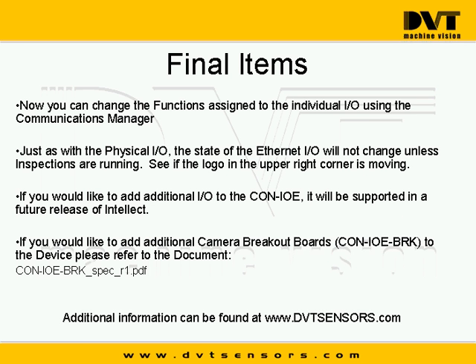Can you say that again about the Modbus? How that's going to communicate? It's going to actually communicate over Modbus TCP instead of just plain Ethernet. All that stuff is actually going to be very transparent to you, because you're going to still continue to set it up in a very similar fashion, but it's actually going to be using Modbus in the background. And by adding additional modules to this particular model that's going to be released, you could have potentially up to 128 I/O points in that particular version.